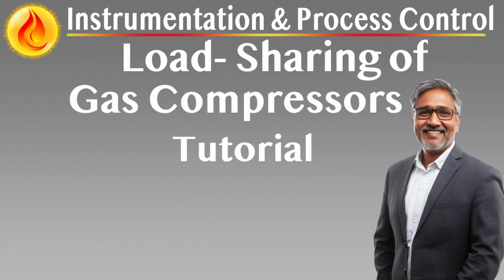Core functional components: station controller, pressure, flow control logic. The station controller acts as the primary regulator of the overall network capacity, either by holding a target discharge pressure or maintaining a desired flow rate at the header. Its output, referred to as the capacity control response, serves as the master command signal for all subordinate controllers in the system. Acts on process variable deviations using advanced PID logic. Generates a unified signal that is distributed to load sharing and anti-surge controllers. Ensures system-wide coherence in response to throughput or pressure demands.